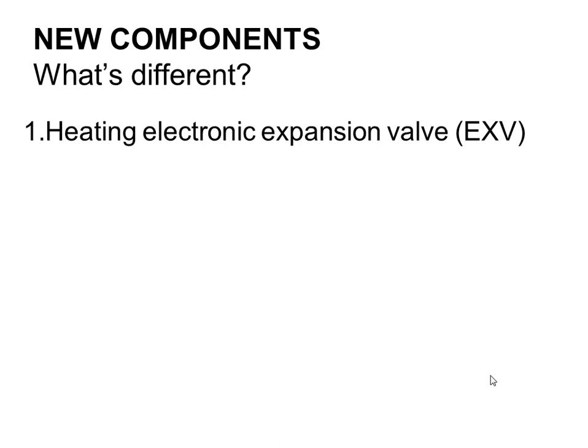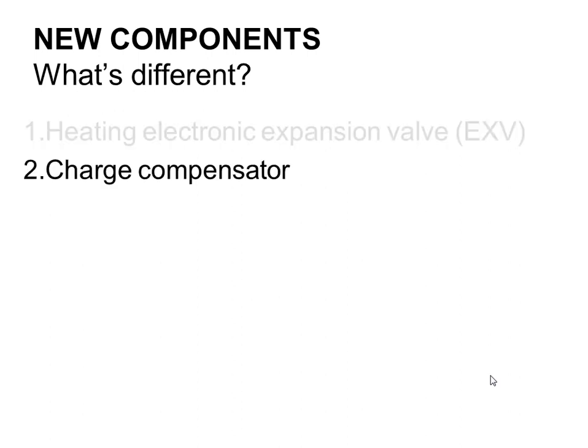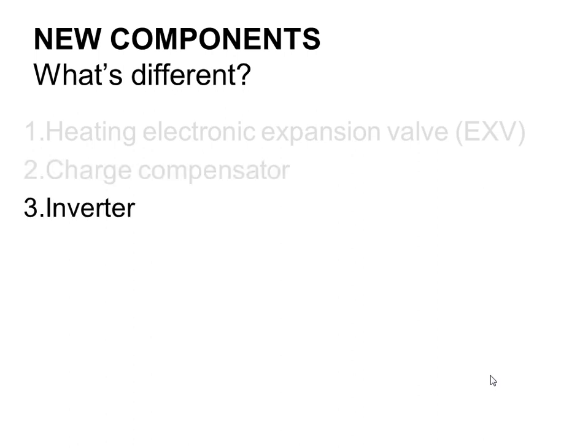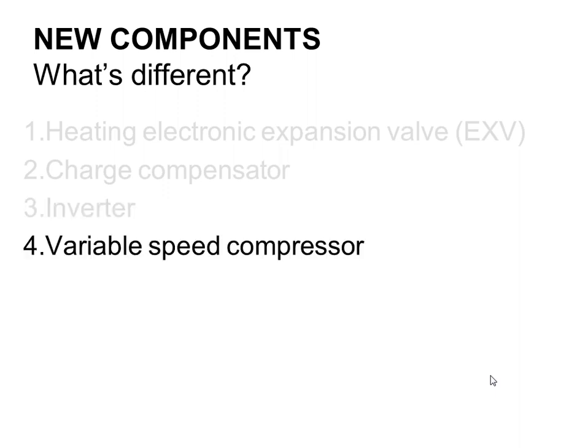In the cooling mode, refrigerant's flowing backwards and it basically is full port open, and in the heating mode we modulate it down. There's a charge compensator, which for lack of a better description, his job in life is to allow us to buffer some refrigerant in the container so we can account for the fact different refrigerant amounts are needed for both heating and cooling so we don't send any gas back to the compressor. It's got an inverter, which is the key to this whole thing. An inverter is basically a VFD. It's a variable frequency drive. We use that to change the frequency of the power coming into the compressor and hence modulate its capacity. The compressor itself is variable speed, ready to accept a signal from that inverter.